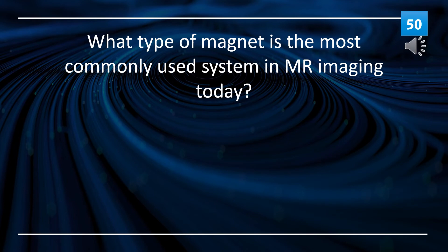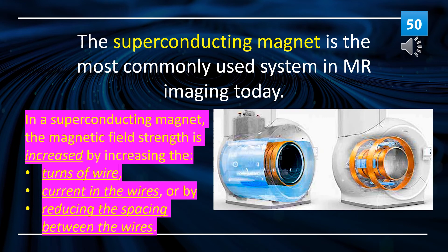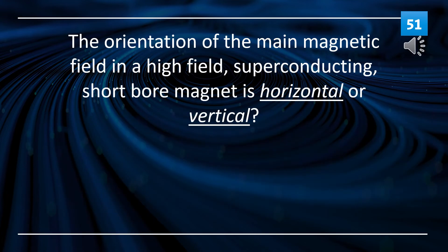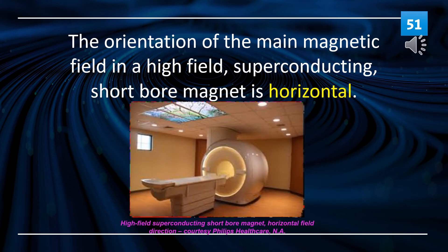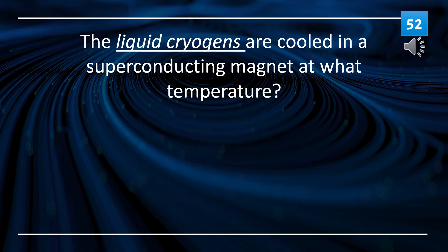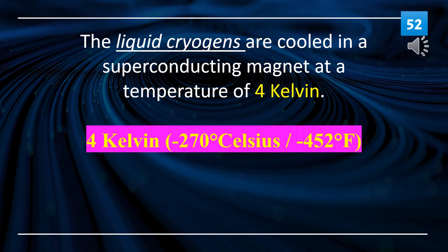The superconducting magnet is the most commonly used system in MR imaging today. The orientation of the main magnetic field in a high field, superconducting, short-bore magnet is horizontal. The liquid cryogens are cooled in a superconducting magnet at 4 Kelvin, which is negative 270 degrees Celsius, or negative 452 degrees Fahrenheit.